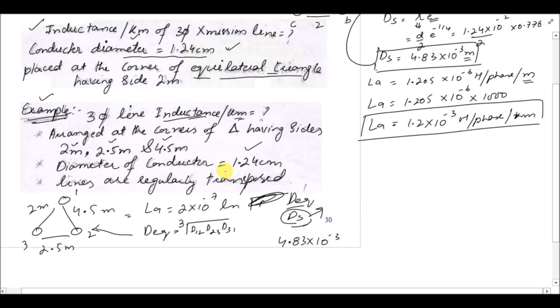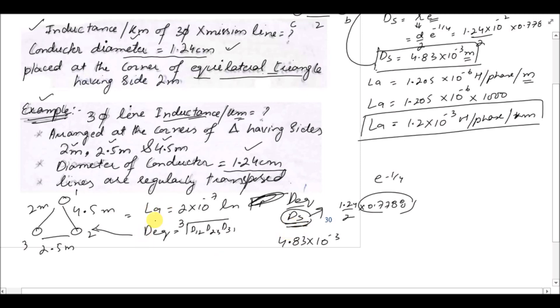Ds is calculated from the conductor diameter: radius = 1.24 / 2, multiplied by 0.778 (which is e^(−1/4)). We always use the fictitious radius when calculating inductance. So Ds = 4.83 × 10⁻³ meters.